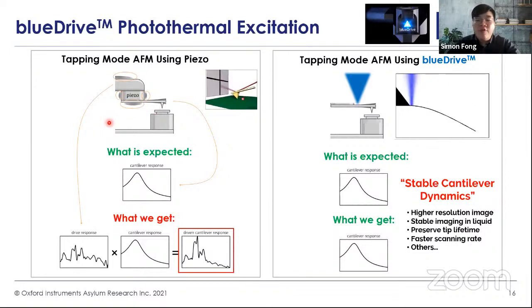However, in a real case scenario, this shake piezo does not only shake the cantilever, but also other parts of the instrument attached to it. This includes the probe holder, some debris, even the environment surrounding the cantilever. As a result, unwanted responses will appear in the tuning process, and this will affect the interactions between the cantilever tip and the sample. Ultimately, in your image, you'll see some artifacts, or maybe noisy images, and you may not see what you want to see on your sample.